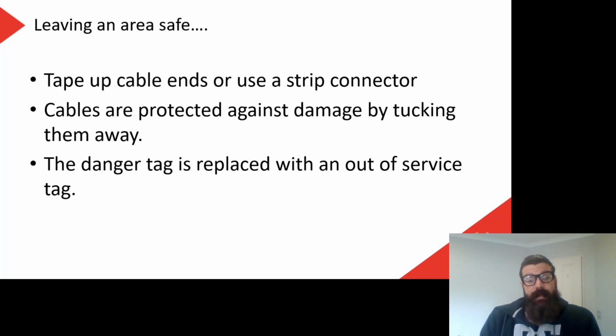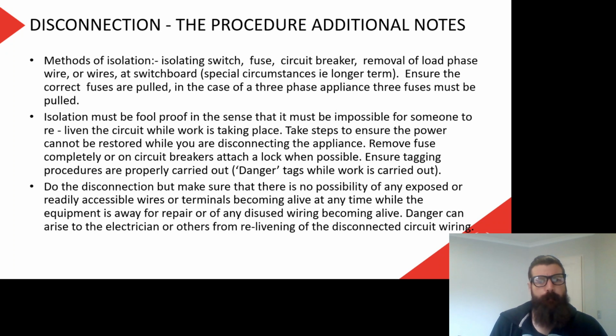Cables are protected against damage by tucking them away, so we don't leave cables hanging out of the walls and over floors and stuff like that. That's good for protecting the cables, but also people. We don't want people to trip over our random cables everywhere. And the danger tag is replaced with an out of service tag, so everyone knows they're not going to switch that on. All right, so some additional notes for the disconnection procedure.